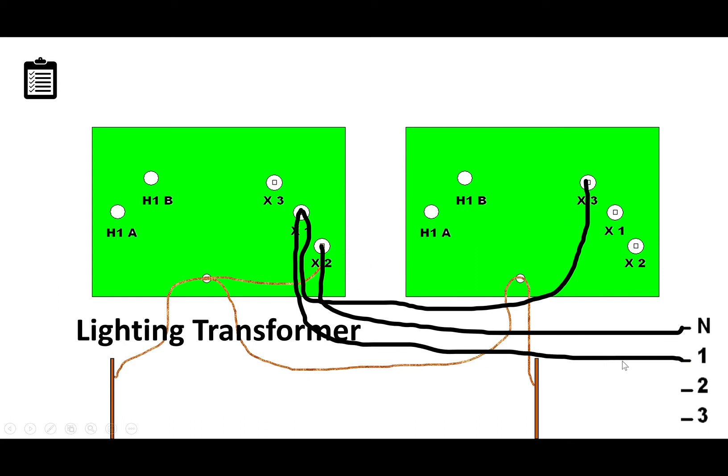The next thing we'll do is connect the secondary lighting leg, one of the first lighting legs, to the X1 of the left hand lighting transformer. The next wire I connect is the next lighting leg coming from the customer to the X3 of the lighting transformer. At this point, the lighting transformer is feeding all of the lighting load.